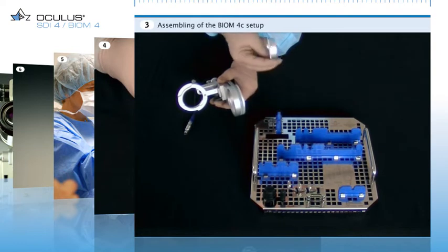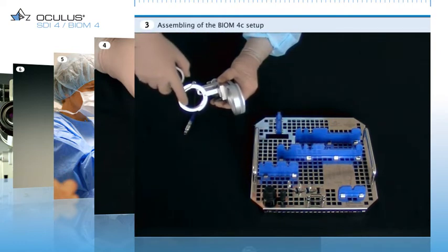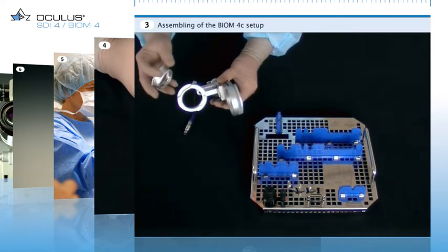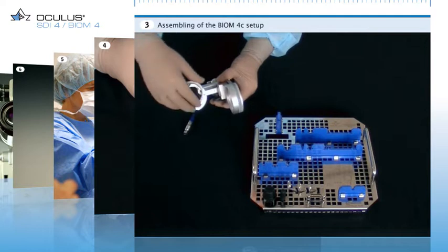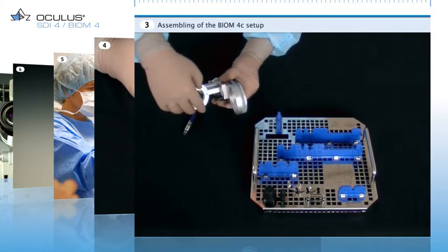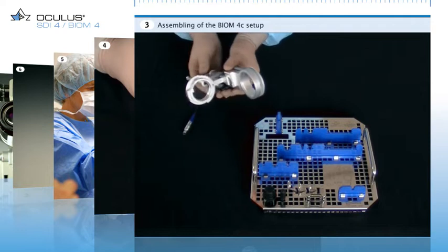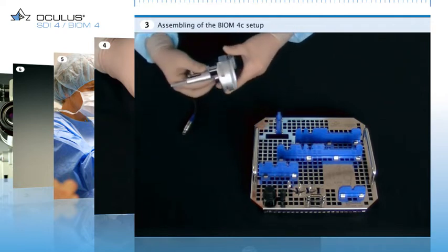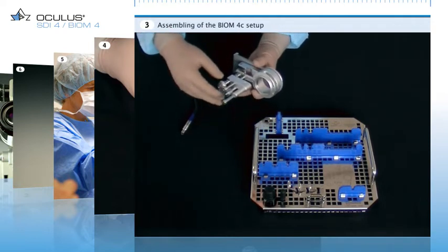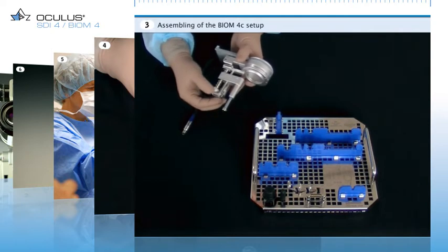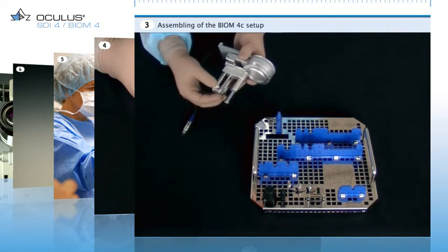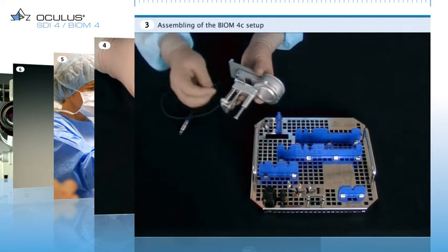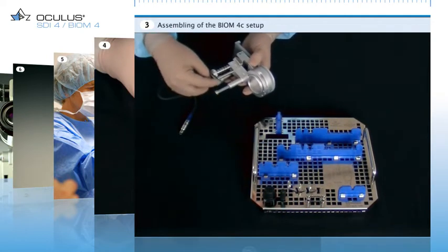Then attach the reduction lens to the BIOM with a quick release fastener. Folding the adapter towards the BIOM reduces the instrument's dimensions and makes it easier to install on the operating microscope. Turn the focus adjustment wheel on the BIOM until the bridge reaches the upper end of its travel. Slip the drive belt for powered focus adjustment over the drive wheel and the two guide rollers.